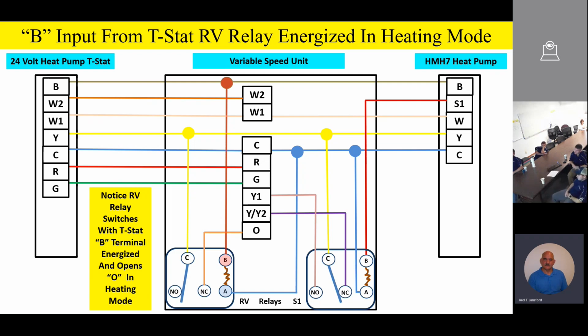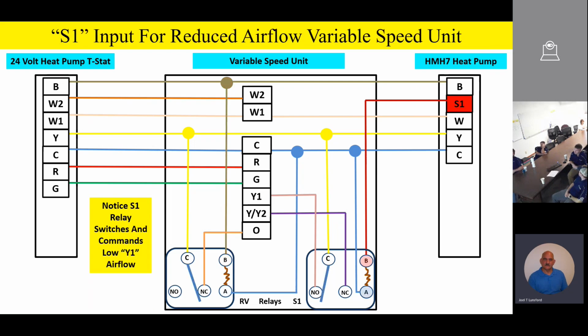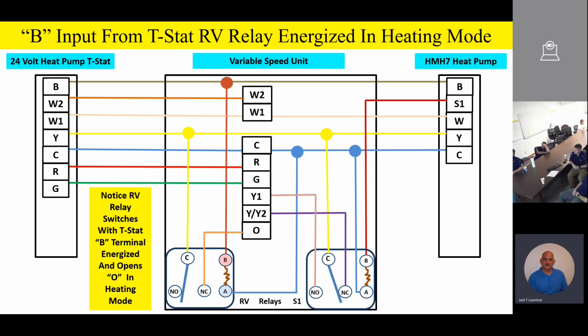When the air handler knows the variable speed product is in the cooling mode, we've got the O terminal. But when we go into the heating mode of operation on our heat pump, we energize the B terminal, bang, we break that O signal, and we disable that O signal and those cooling advanced functions. Any questions or comments on the relay logic, how we're reducing airflow, and how we're hooking these things up to a variable speed product? Everybody in good shape? Okay.